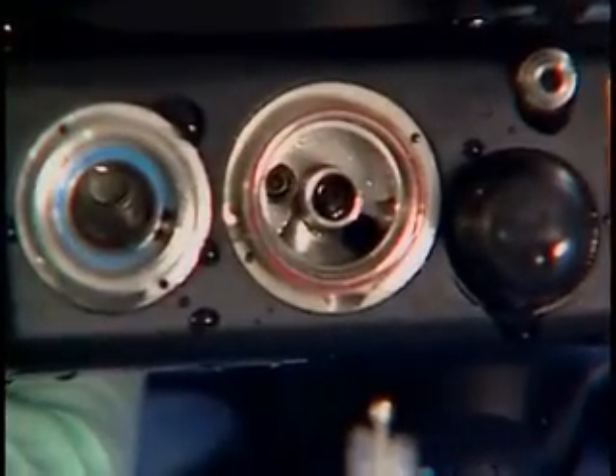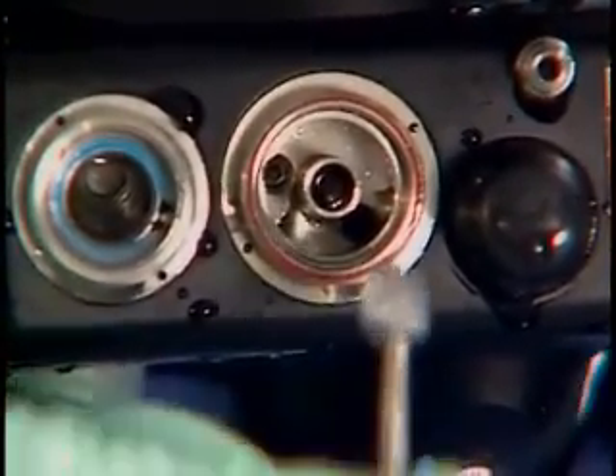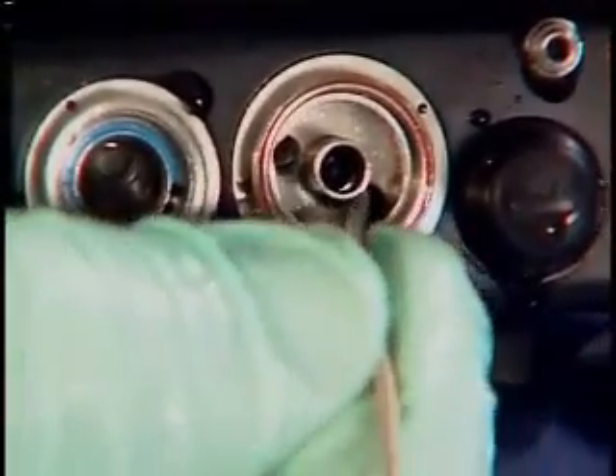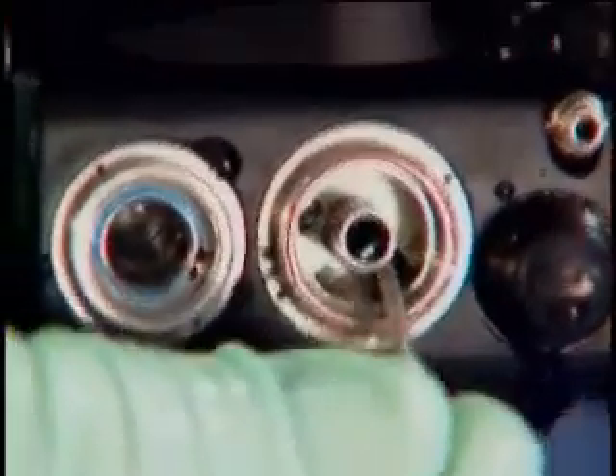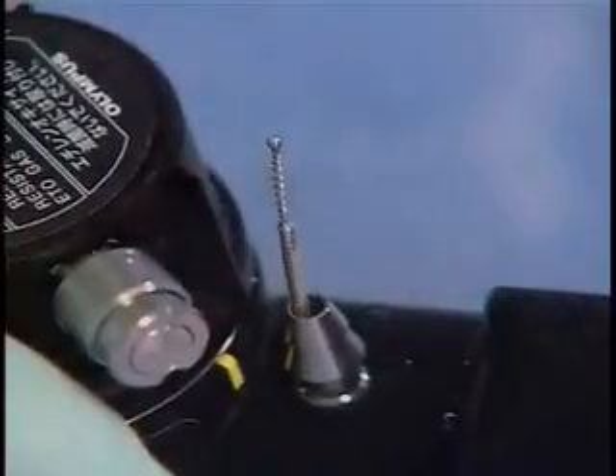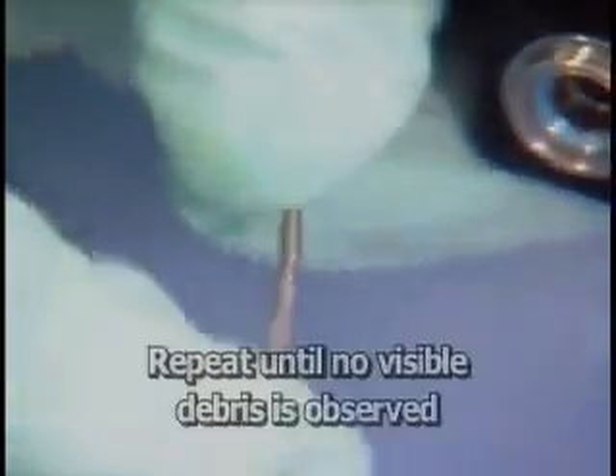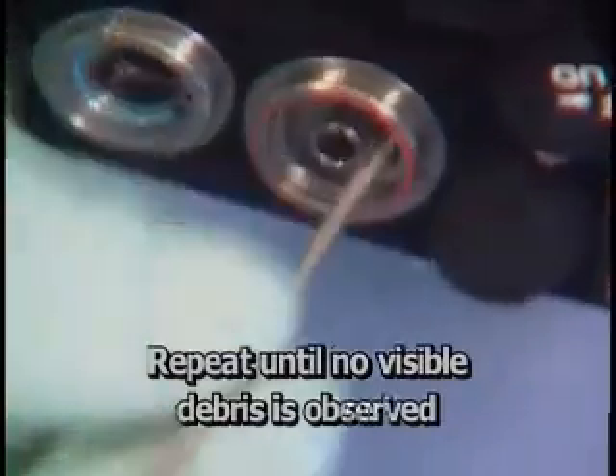To brush the suction channel within the universal cord, insert the brush into the upper opening in the back of the suction cylinder. Pass the brush through the universal cord until it emerges from the suction connector. Clean the bristles and withdraw the brush. Once again, clean the bristles and repeat until no debris is observed on the brush tip.